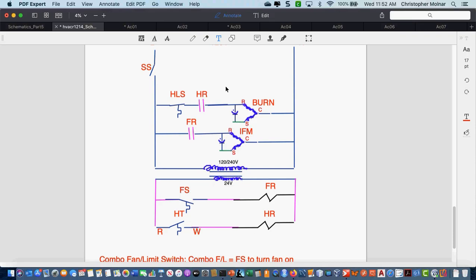In series with your motor? You are right. It is in series with my motor. What could fail and actually cause my motor to continue to run if I put this limit switch on the low voltage side? What could fail?